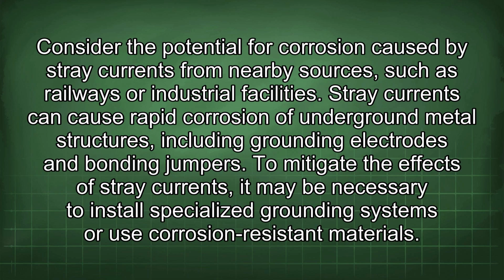Consider the potential for corrosion caused by stray currents from nearby sources, such as railways or industrial facilities. Stray currents can cause rapid corrosion of underground metal structures, including grounding electrodes and bonding jumpers. To mitigate the effects of stray currents, it may be necessary to install specialized grounding systems or use corrosion-resistant materials.